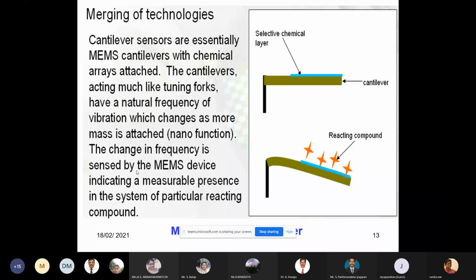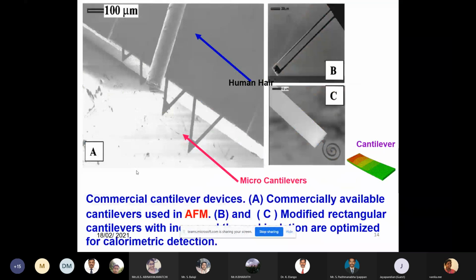Static mode is only deflection. In dynamic mode, if you are vibrating the cantilever and there is a change in mass, then there is a resonance frequency shift. This is a nano function. This is what people are using for many applications, micro cantilever or nano cantilever. The cantilever has a wider application area nowadays. Then these are the commercial cantilevers available. Left-hand side shows the triangular type, an atomic force microscopy probe.